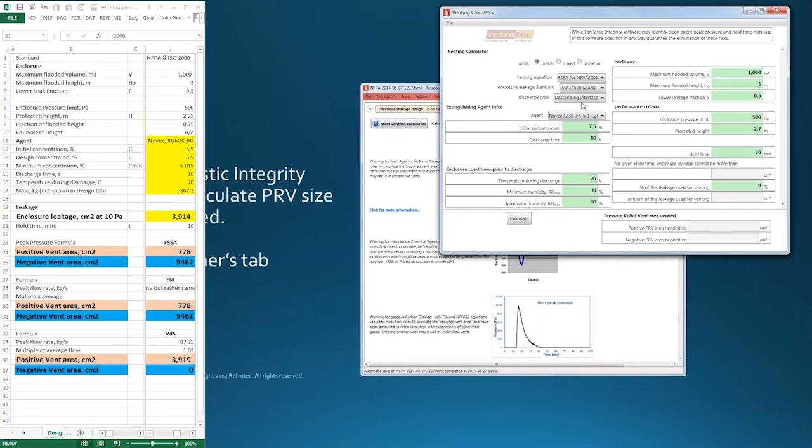Go back to the FSSA equation here, and we're putting in 5.9%. Probably a little bit high for what we typically do in North America. I think we're usually closer to about 4.5%, but you can put any concentration that you want there. We have a humidity range from 30 to 80%. I think the default here might be 80. This evaluation, we're using 60.